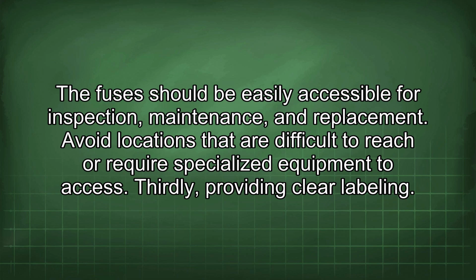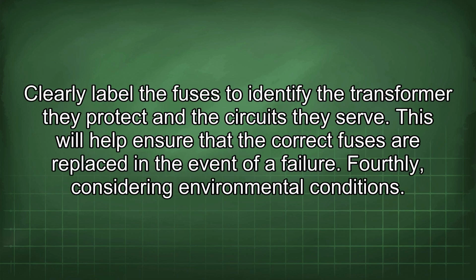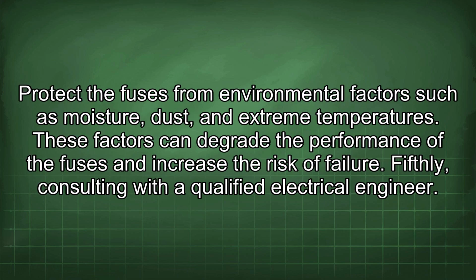Thirdly, providing clear labeling. Clearly label the fuses to identify the transformer they protect and the circuits they serve. This will help ensure that the correct fuses are replaced in the event of a failure. Fourthly, considering environmental conditions. Protect the fuses from environmental factors such as moisture, dust, and extreme temperatures. These factors can degrade the performance of the fuses and increase the risk of failure.